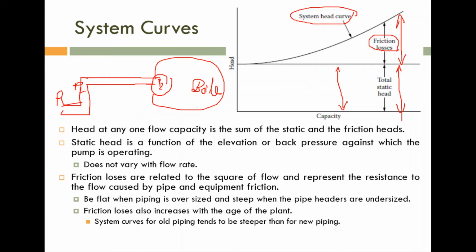So please note, the system curve depends upon a number of factors. It depends upon whether there is any static head difference inside the pipeline, like this one. It also depends upon the application of that fluid transportation, where we are transporting that fluid, whether we are transporting the liquid to a boiler, etc. If it is a boiler, definitely the static head will increase.